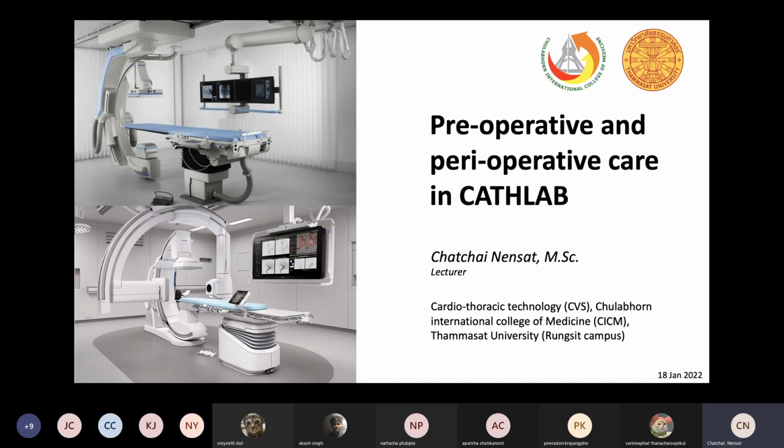C arms, right? So when the interventional cardiologist injects the contrast into the patient to examine the coronary artery, the image that we generate just uses a single X-ray beam generation. It just hits the button one time, so you will get two images.